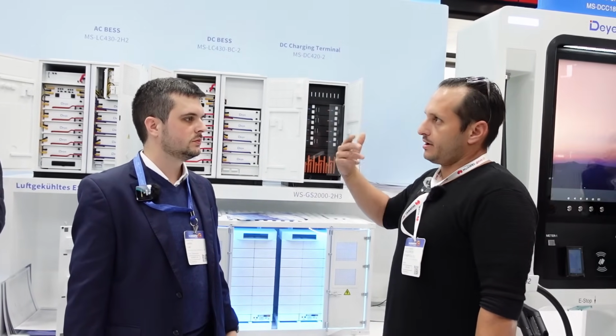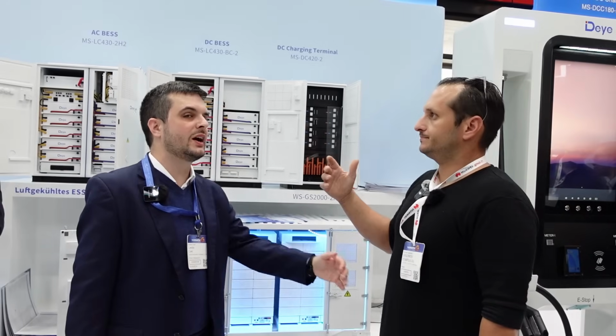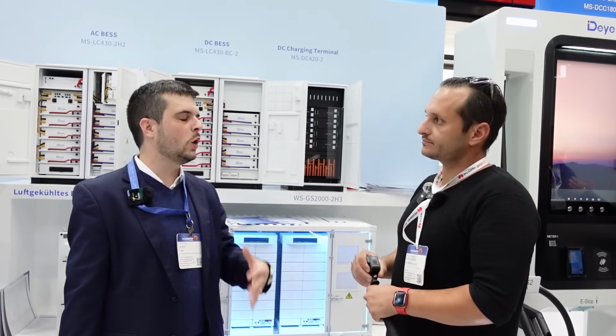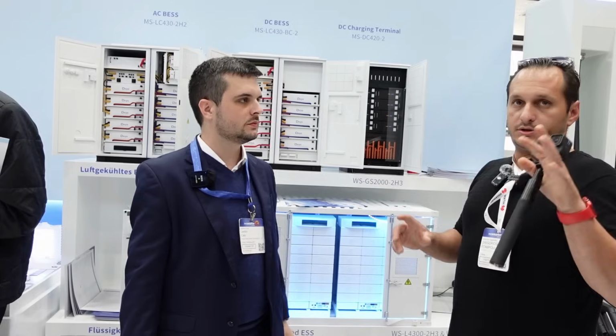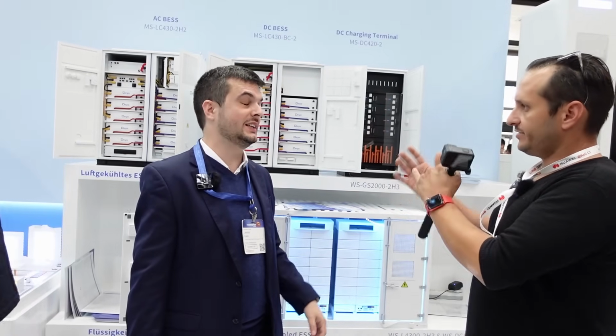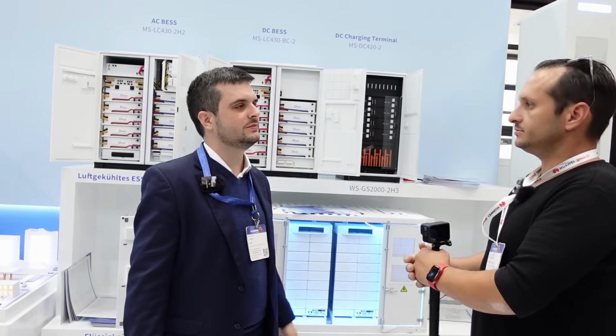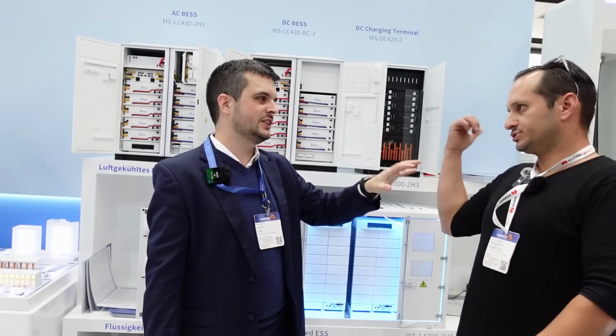You take into account the problem—you have the fire extinguisher, the cooling, all the alarms, the temperature control, everything outdoor. You take the cabinet and install it outdoor, in rain or snow, no problem. Wind, dust—everything can handle this. This is why we see more cabinets in Europe. Outside Europe, we see more the system I showed before, where the battery and inverter are together.